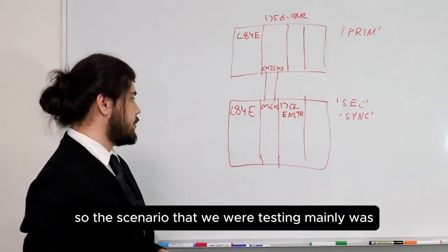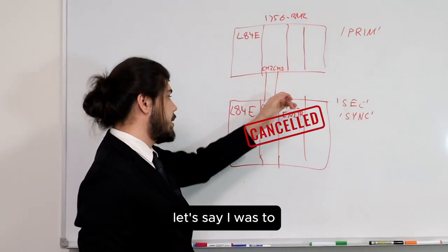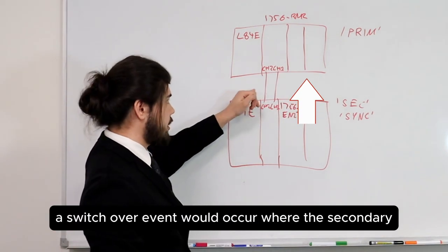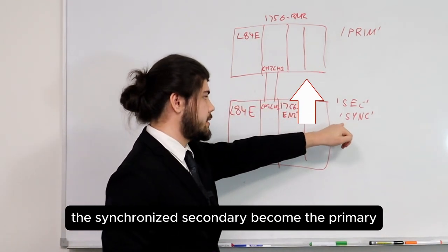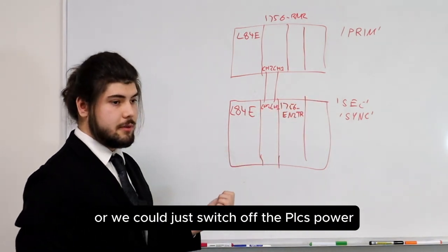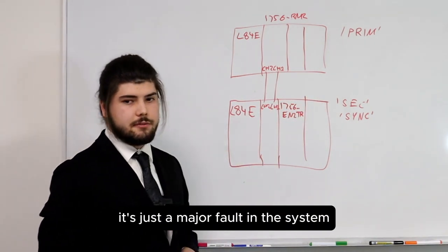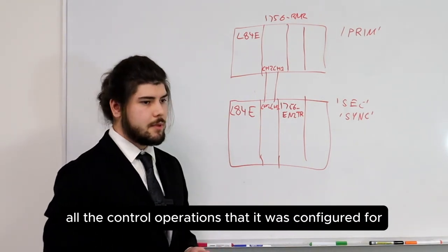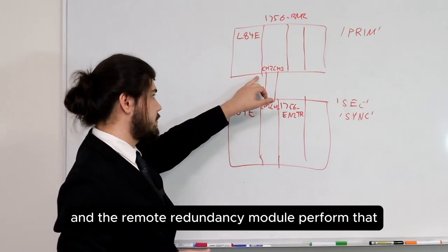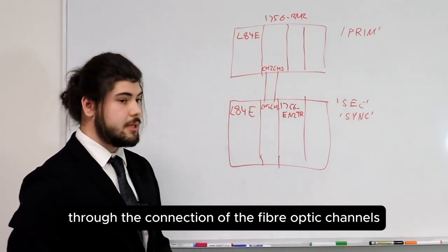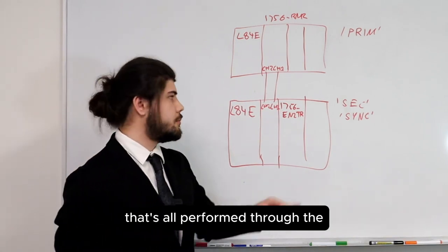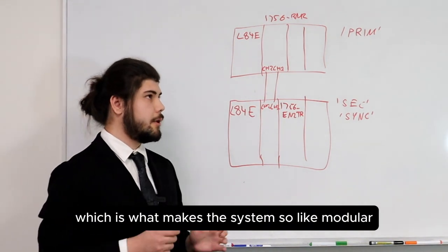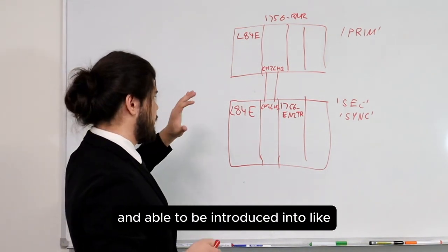The scenario we were testing mainly was communication loss. If I were to unplug an Ethernet cable from the communication module, a switchover event would occur where the synchronized secondary becomes the primary. Or we could switch off the PLC's power — a power loss. More generally, it's just a major fault in the system. If the main controller is no longer able to perform all the control operations it was configured for, it will detect that and the redundancy module will perform the switchover through the fiber optic channel connections. That switchover is not performed through the Ethernet — it's all performed through the fiber optic channels, which is what makes the system so modular.